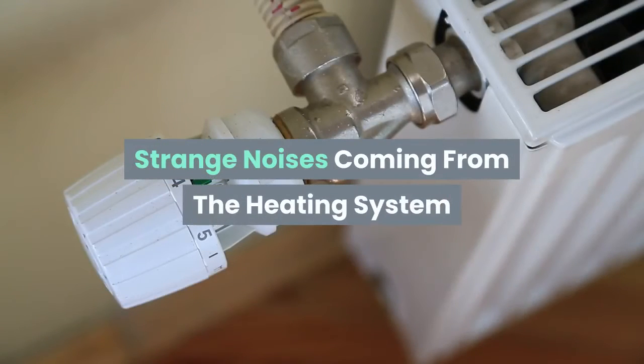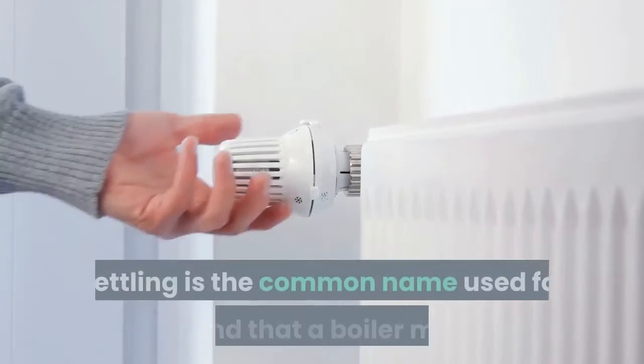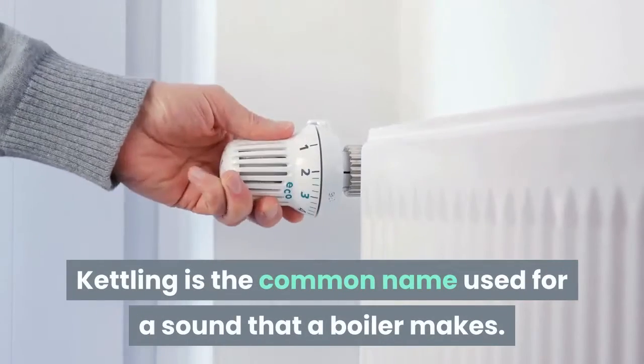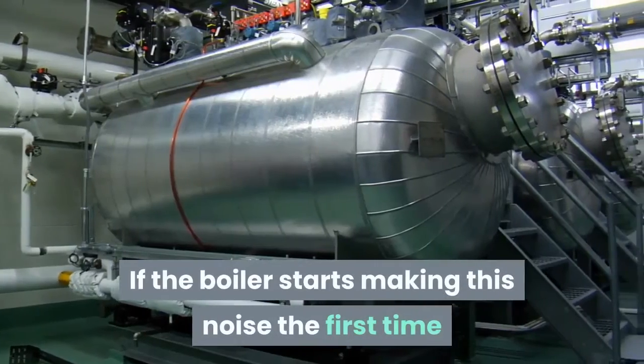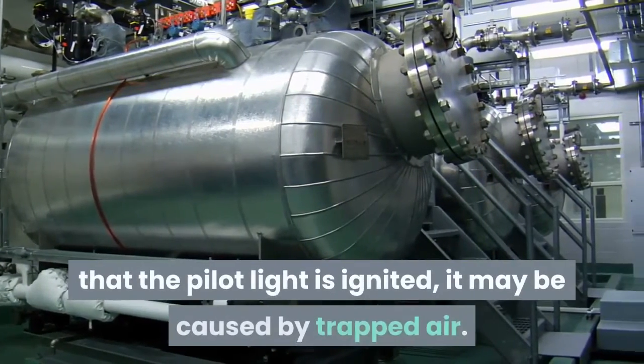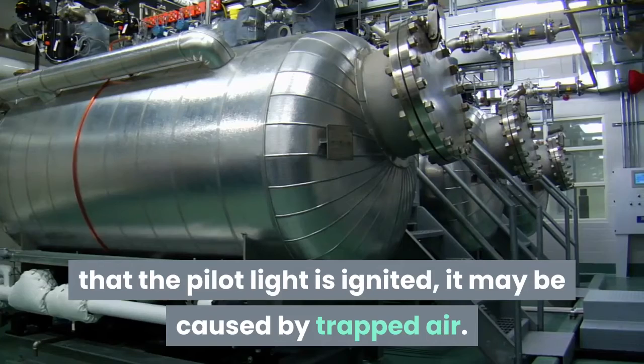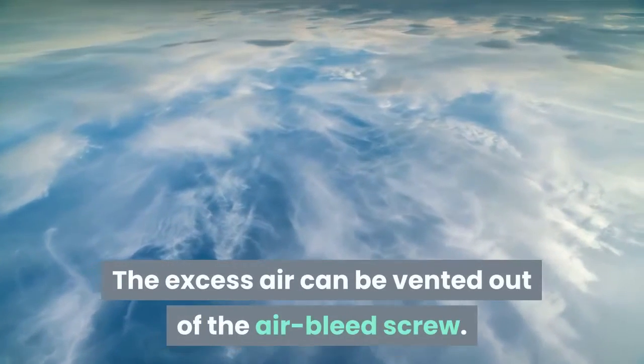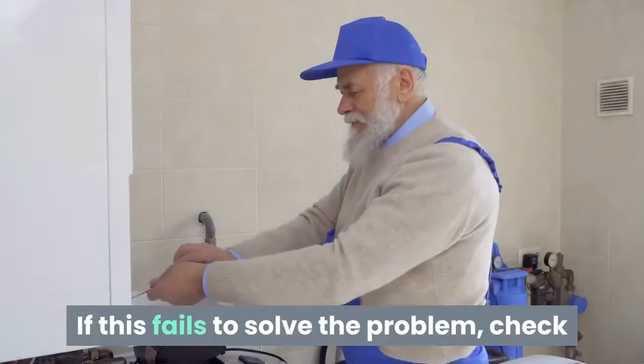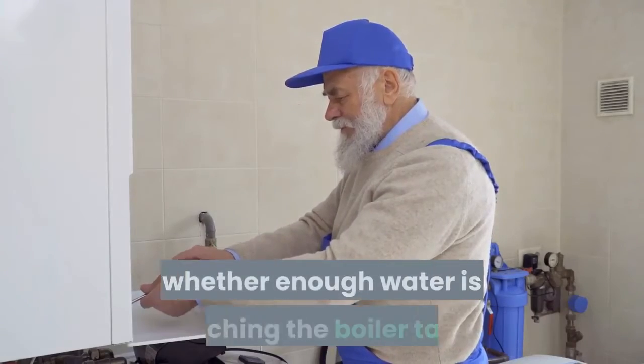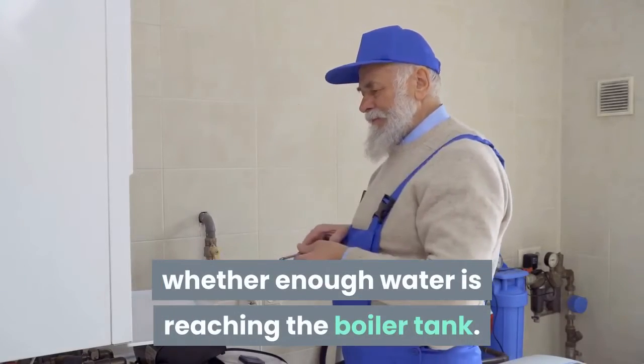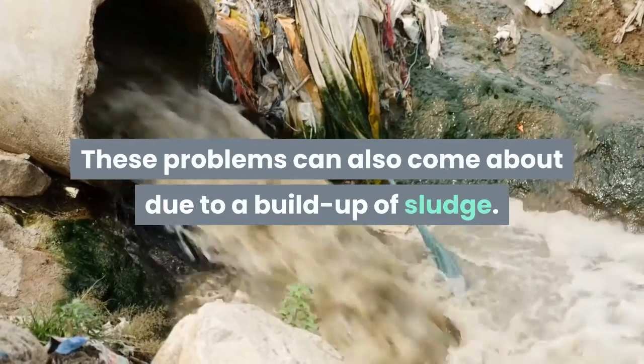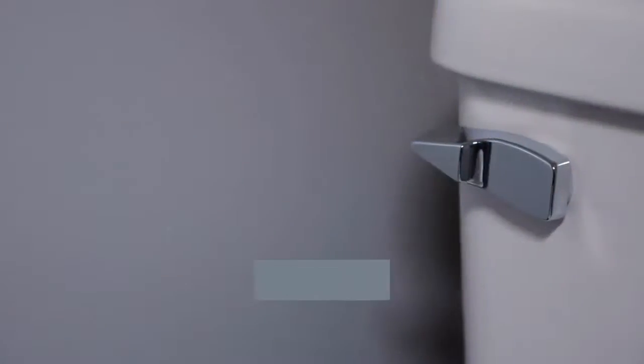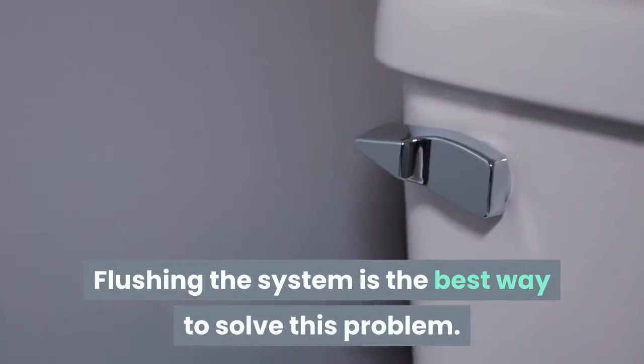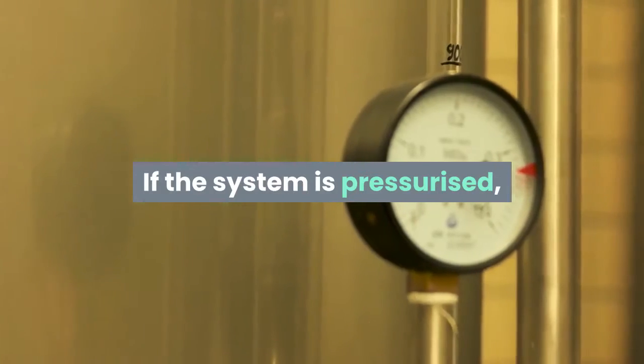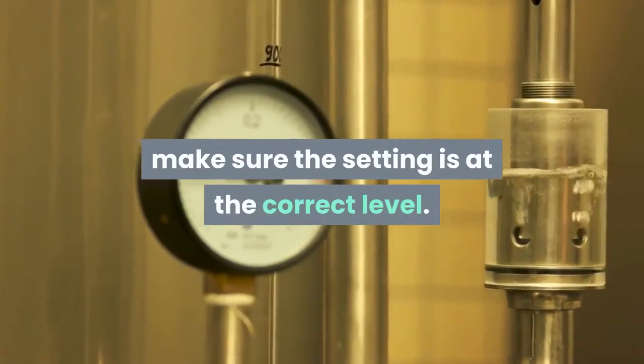Strange noises coming from the heating system. Kettling is the common name used for a sound that a boiler makes. If the boiler starts making this noise the first time that the pilot light is ignited, it may be caused by trapped air. The excess air can be vented out of the air bleed screw. If this fails to solve the problem, check whether enough water is reaching the boiler tank. These problems can also come about due to a buildup of sludge. Flushing the system is the best way to solve this problem. If the system is pressurized, make sure the setting is at the correct level.